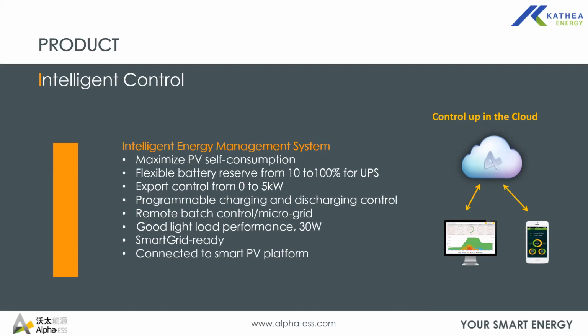And the system is supplied with a meter, a single phase meter or a 3-phase meter. This meter will be installed at the grid incomer soon after your mains incomer, such that it measures everything in the house, because it's the one which is responsible for giving the inverter the set point to produce. So that meter would help the system to limit to self-consumption, that is to only supply load to your premises. If you are to feed into the grid, then the meter will tell you how much you are feeding back to the grid.